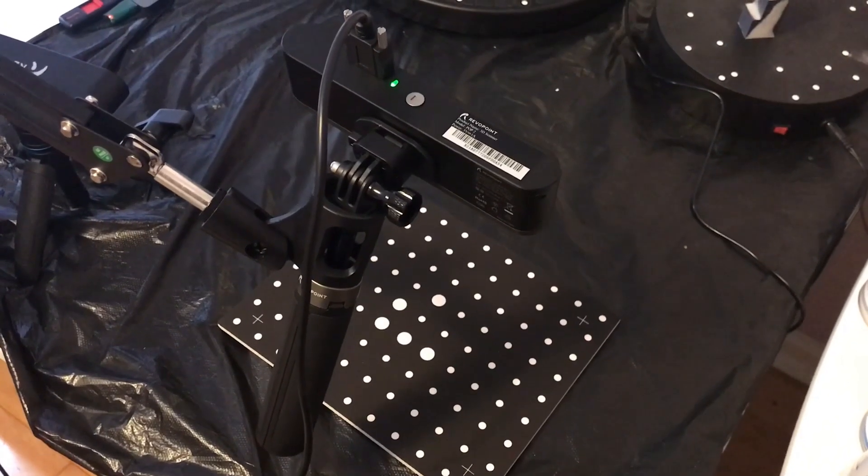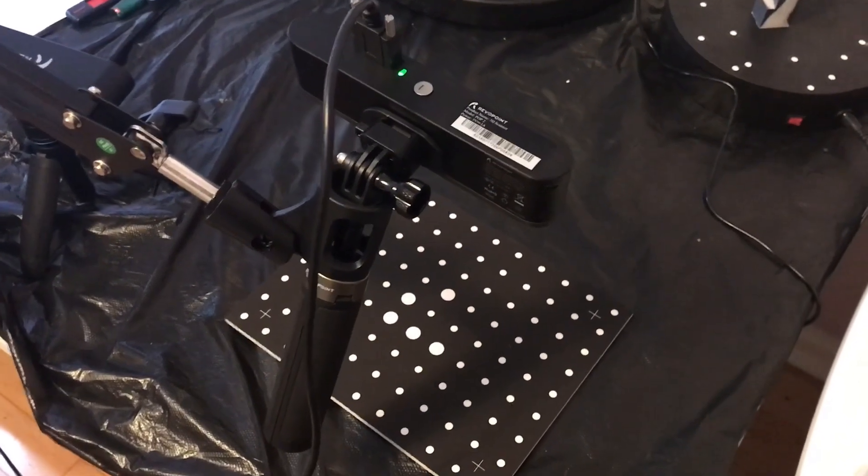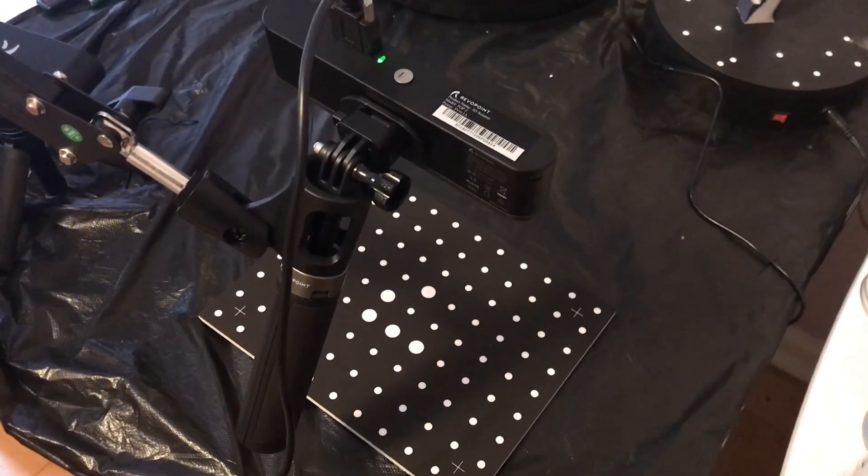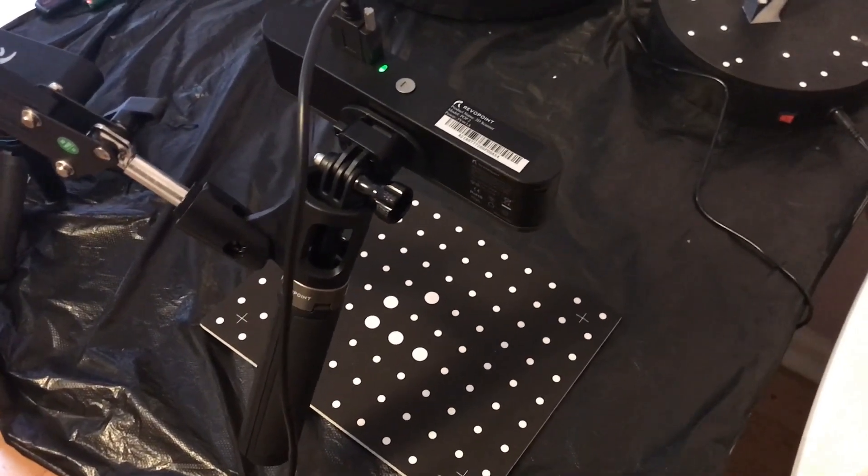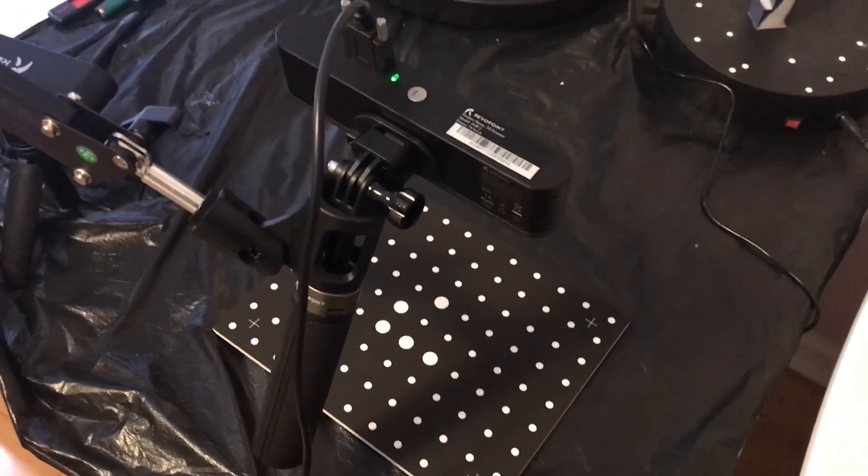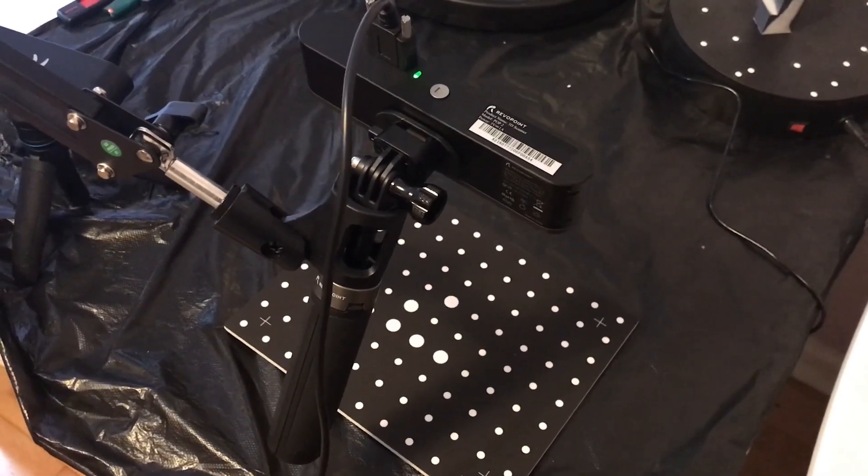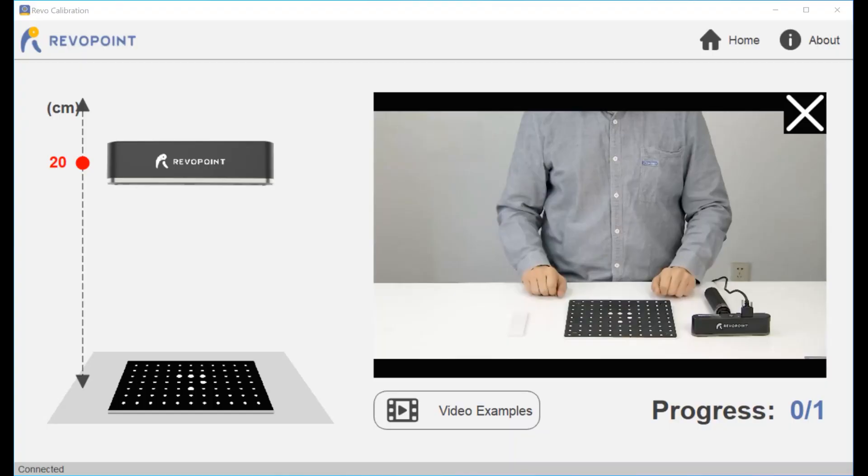This is my accuracy check. I've got the calibration board and I have the camera set up 20 centimeters above the board. Before I do any tests, I want to make sure the unit meets its requirements.